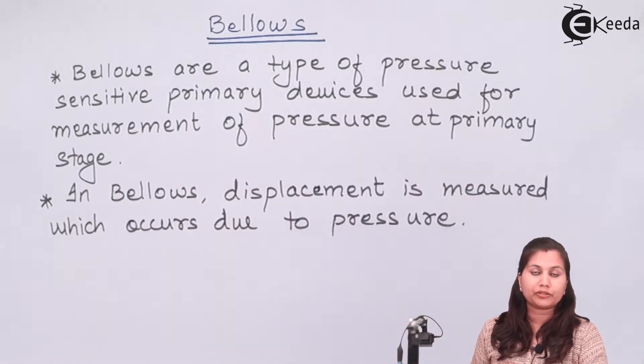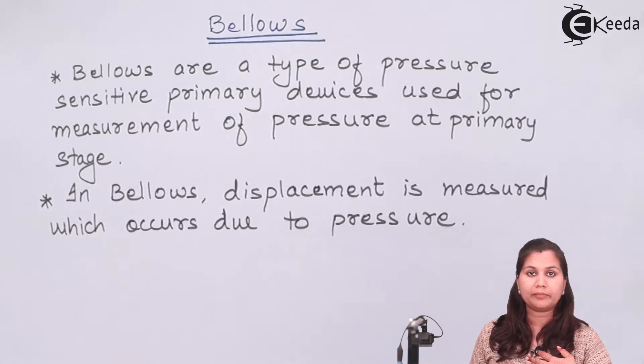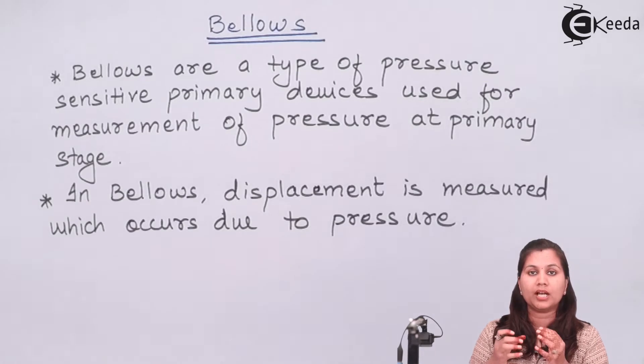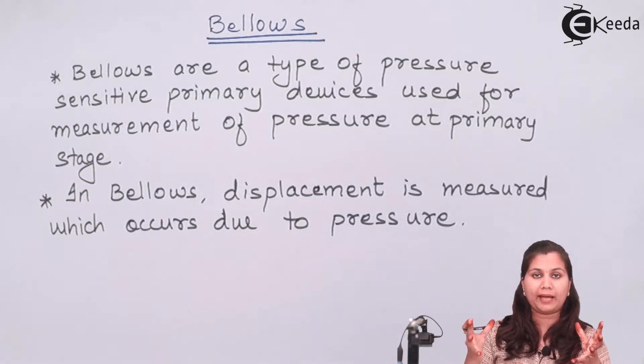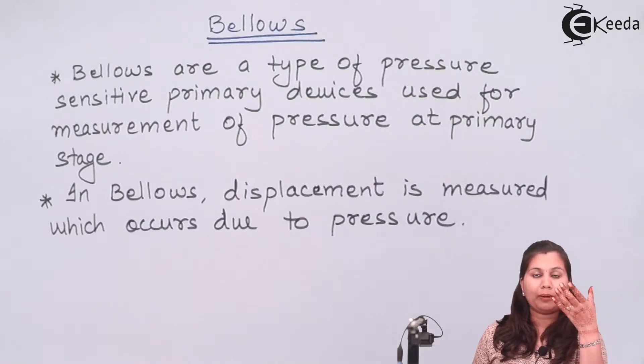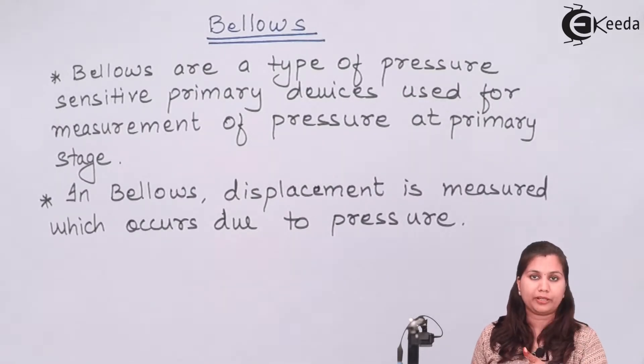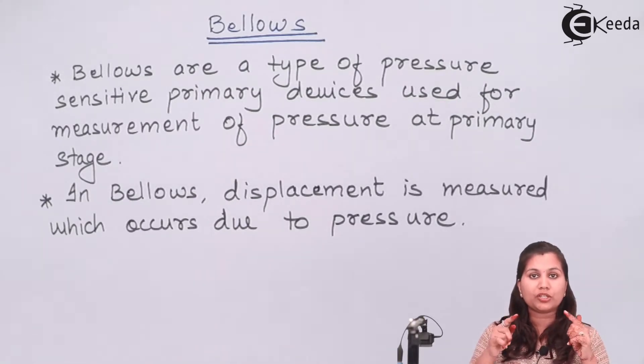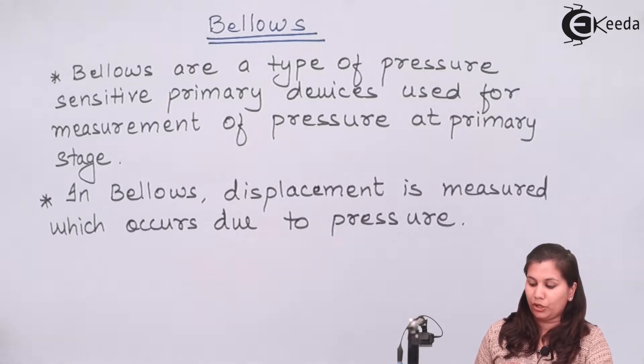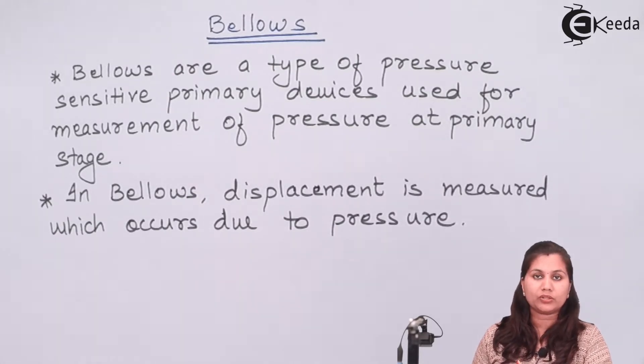Bellows are used for the measurement of pressure. How they measure the pressure — because bellows are made up of elastic material, so when the pressure is applied to the bellows, the elastic material is going to expand or change its shape. So by measuring that change in shape we can measure the pressure, because the shape change of the bellows will be proportional to the applied pressure. This is the working principle of the bellows — how they measure the pressure of the fluids.